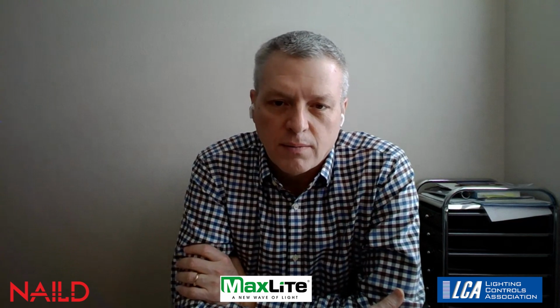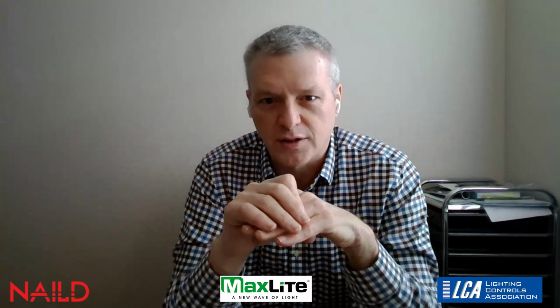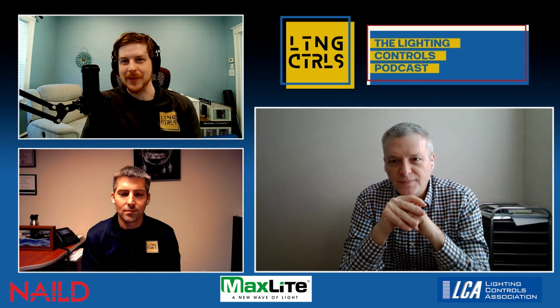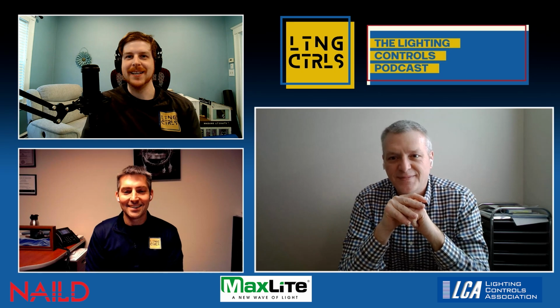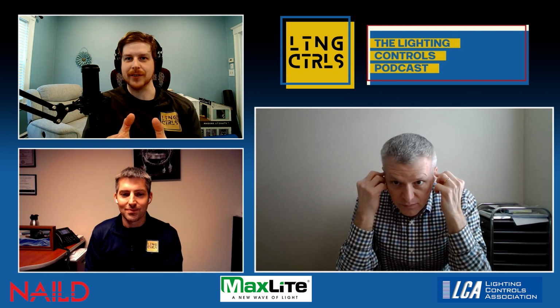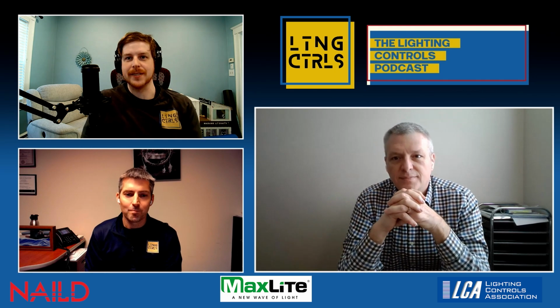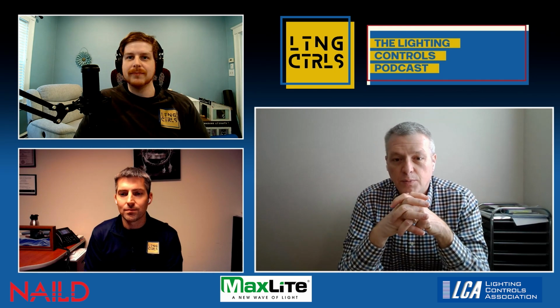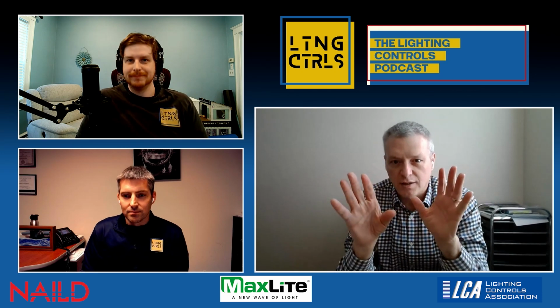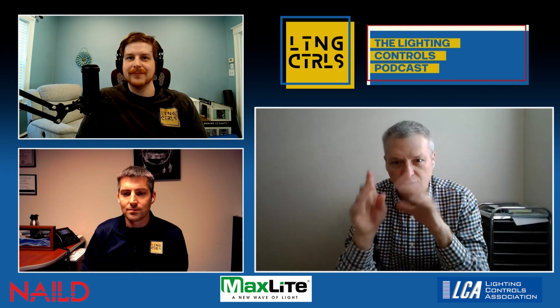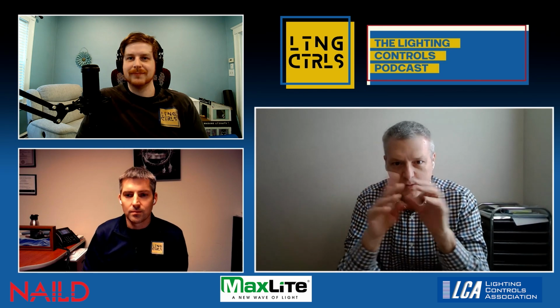So we've got a test project going on right now using LLC. In the basic gist of it, it's got D4I in it, which is nice because two-way communication is important as we go through the digital world. D4I is a standard from Dali that regulates how the driver communicates out to a Dali system. It gives us two-way communication, which is key, not 0 to 10 volt, which is a single analog type of system.